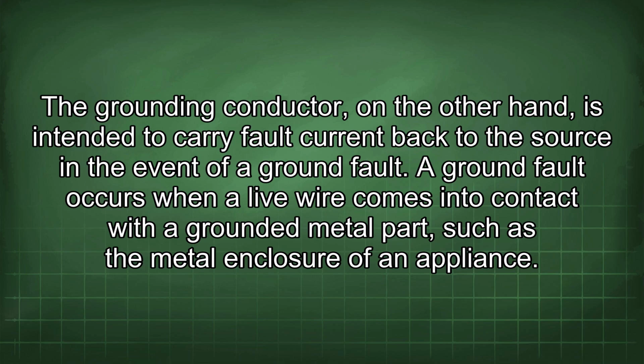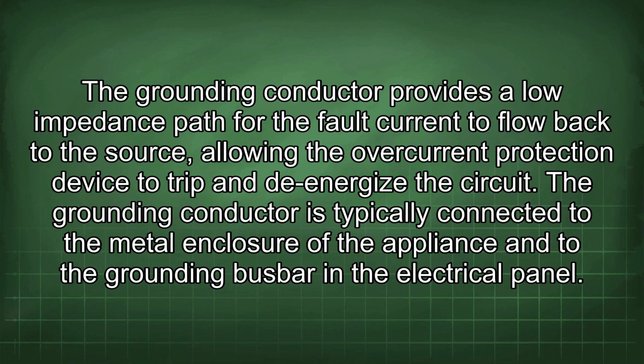A ground fault occurs when a live wire comes into contact with a grounded metal part, such as the metal enclosure of an appliance. The grounding conductor provides a low impedance path for the fault current to flow back to the source, allowing the overcurrent protection device to trip and de-energize the circuit.